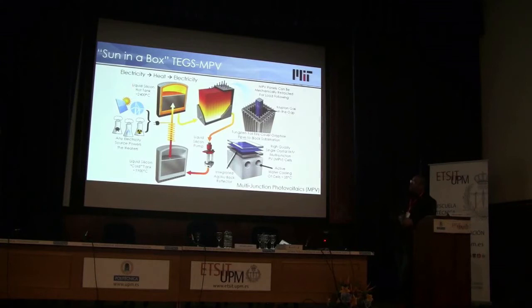When you would like to make electricity again, you pump the liquid out of the hot tank through the power conversion module, which has a number of things inside. The liquid flows through a bank of tubes, so you can think of it like a heat exchanger—all this tubing is made out of graphite.